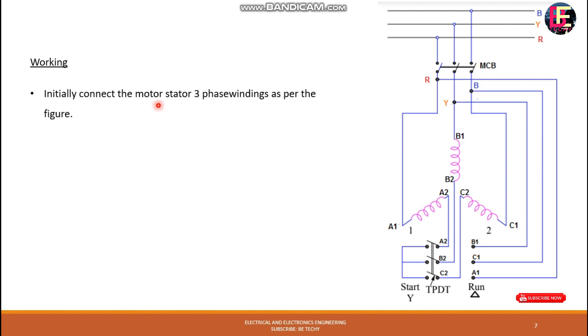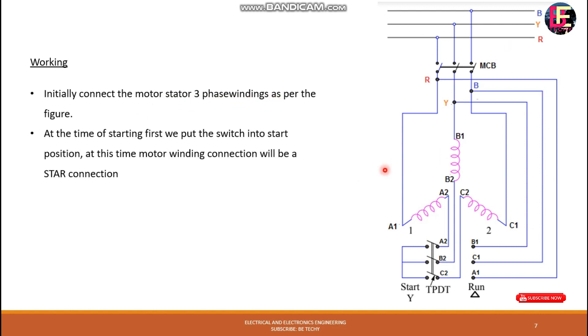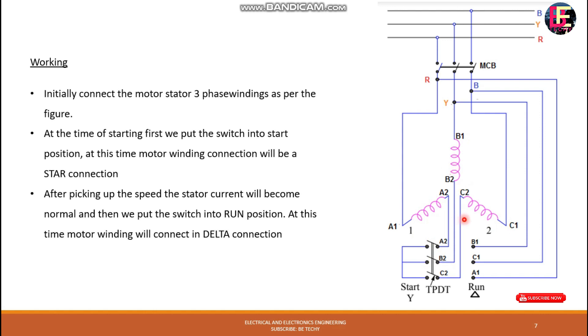Initially, we connect the motor stator 3-phase winding as per the figure. At the time of starting, first we put the switch into the star position — at this time the motor winding connection will be a star connection. Then we put the switch into the run position, and at this time the motor winding will be a delta connection.